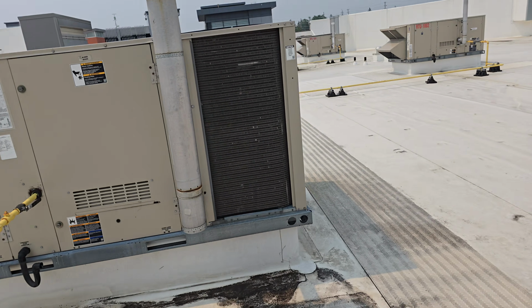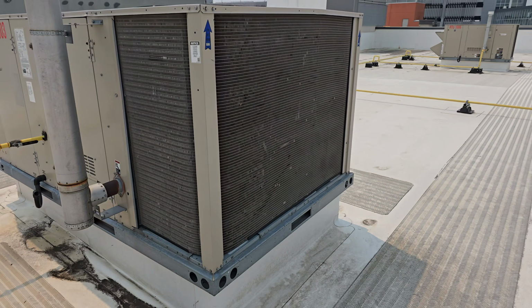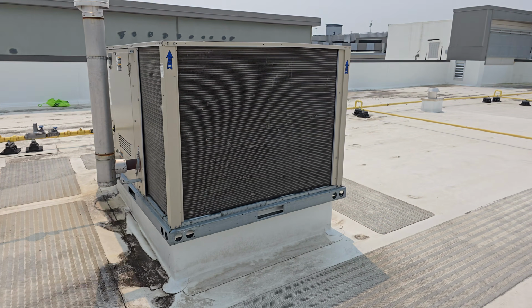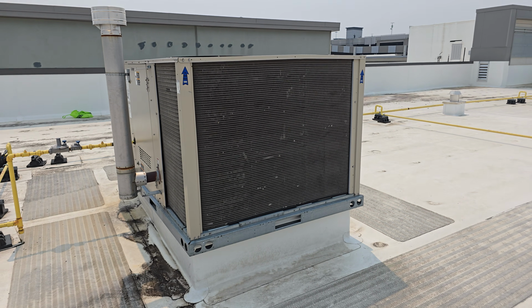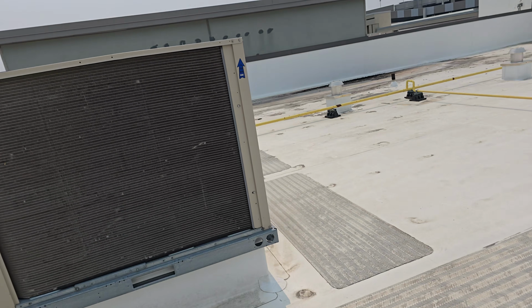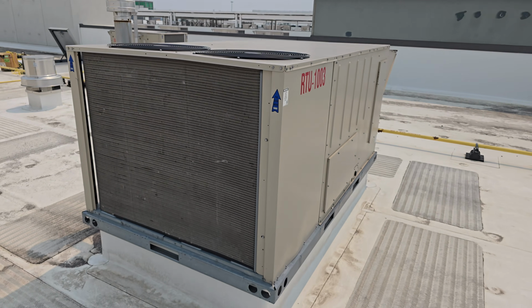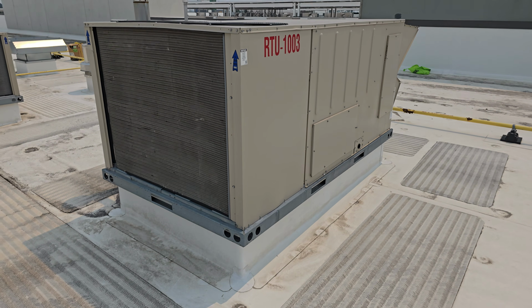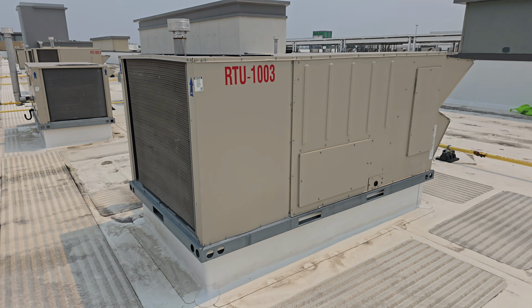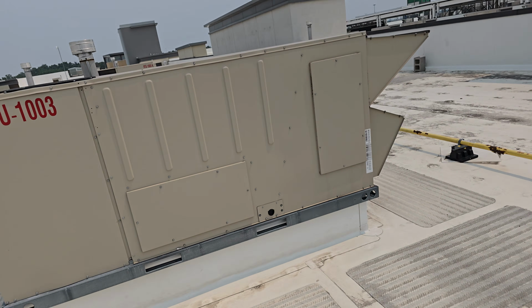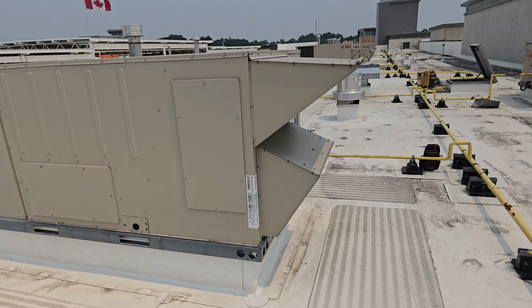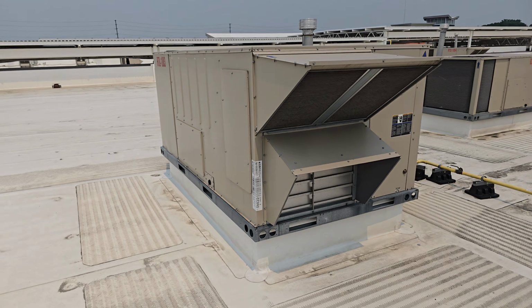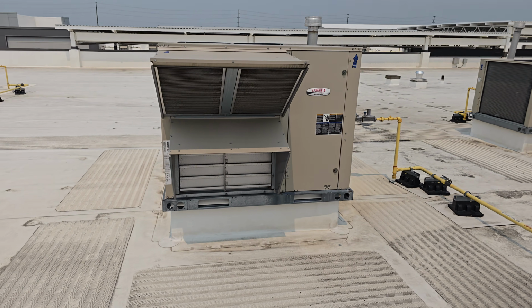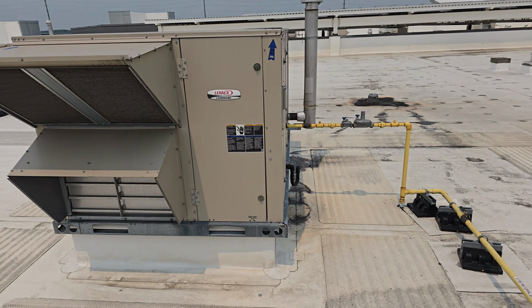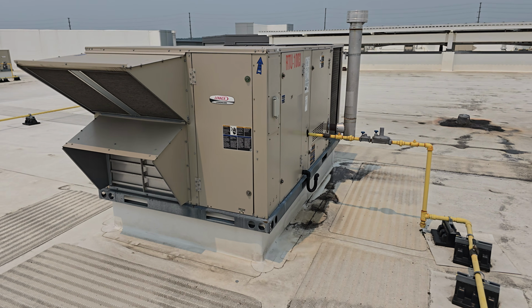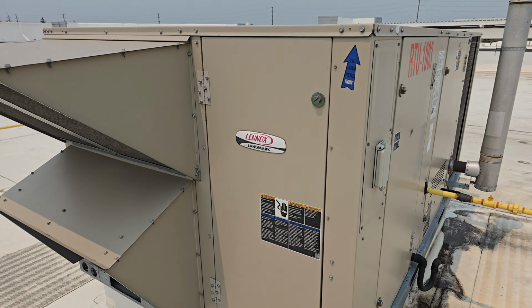So I went to the electrical room to see if the unit had tripped off on the main electrical panel. But looking at it, there was no trip off from the electrical panel. So I came up on the roof to see what's going on. I'm going to walk you through how we'll see what's going on here. Okay, so this is my electrical section.